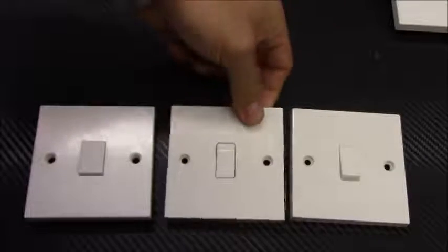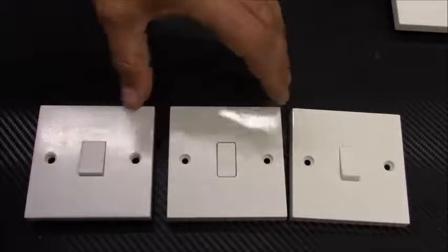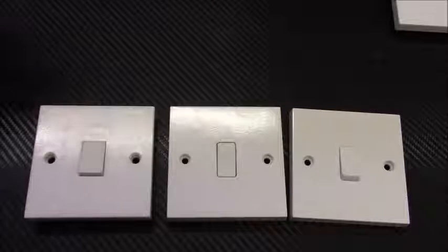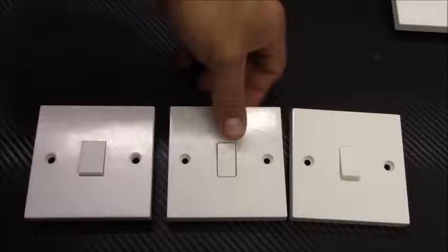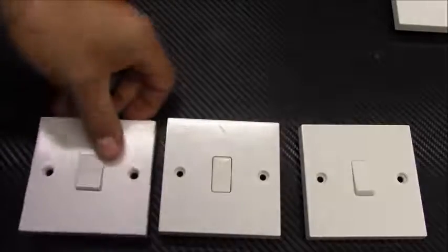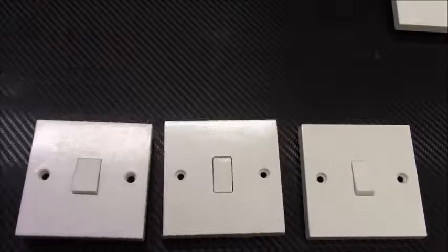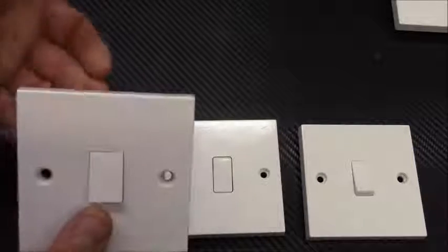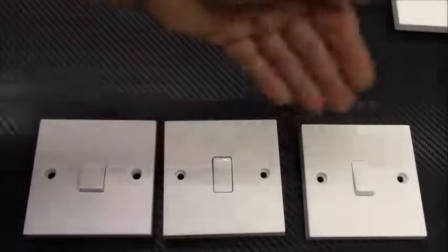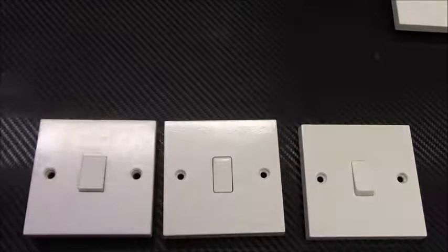So you just place it in between these 2 in different locations, and then you can control one light or set of lights. If you want 4-way switching, you use 2 of these in between the 2-way switches. There's no such thing as a one gang 3-way switch. For 3-way switching, you need to use all 3 switches.